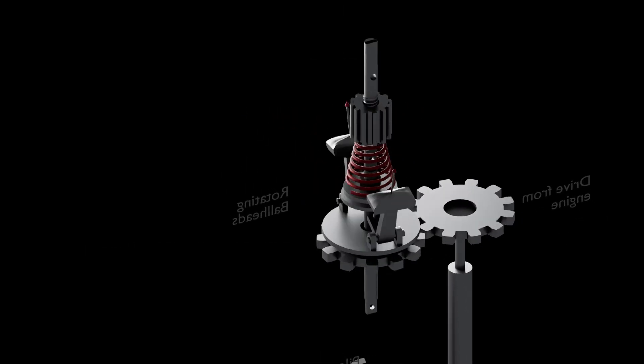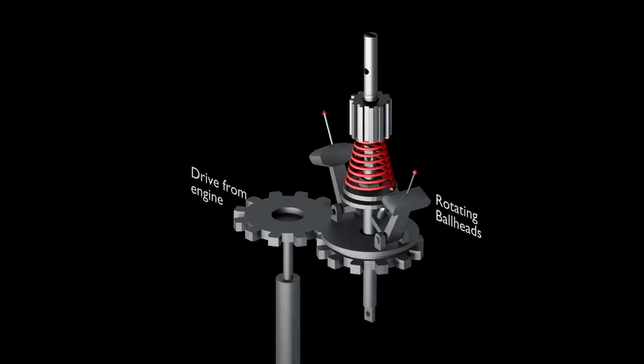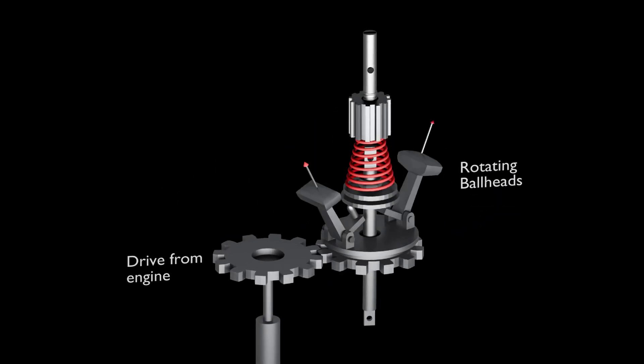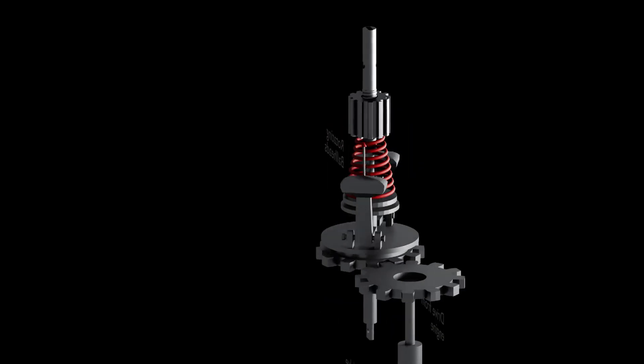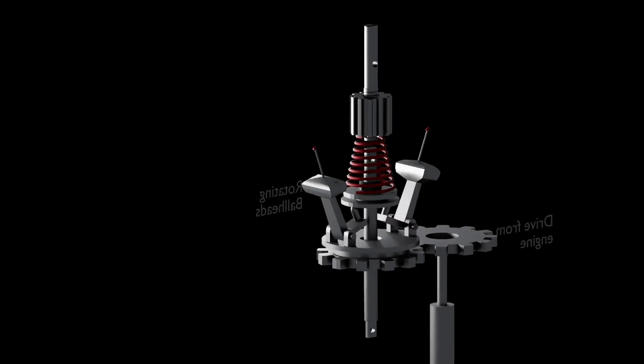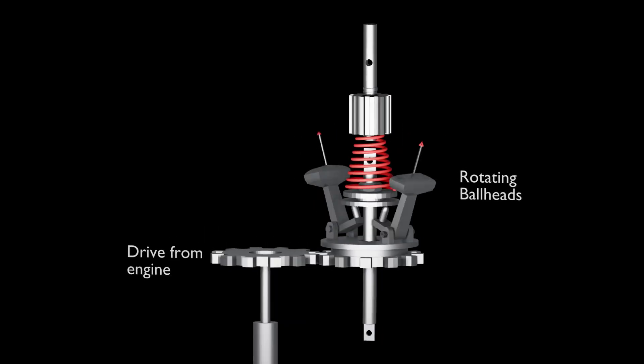However, when engine runs up to say 620 RPM, the flyweights rotate at higher speed and move further away from the axis of rotation. The opposite happens when engine speed drops to say 580 RPM. Flyweights, due to lower centrifugal force, come closer to the axis.